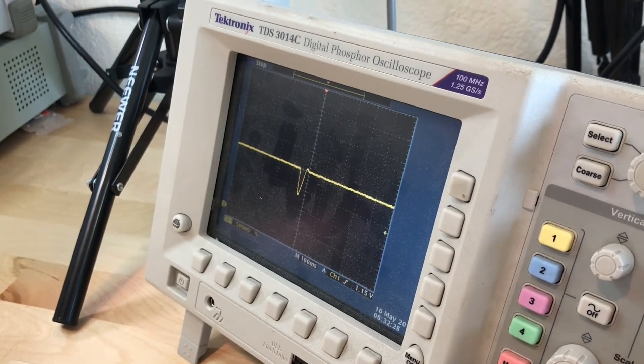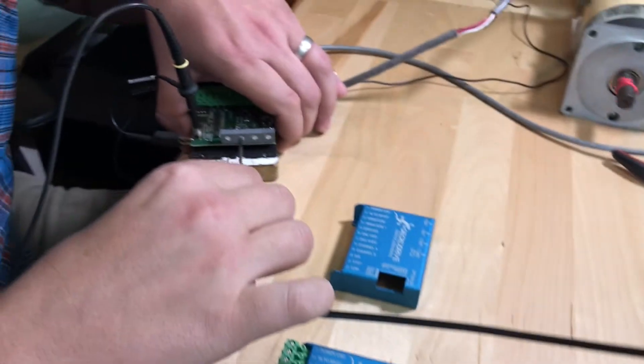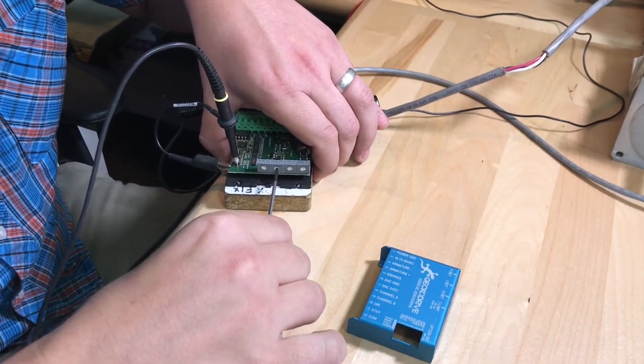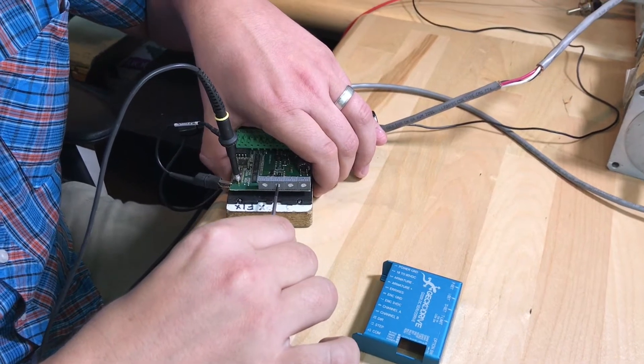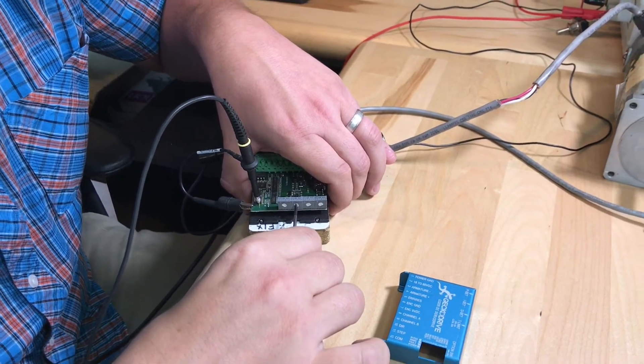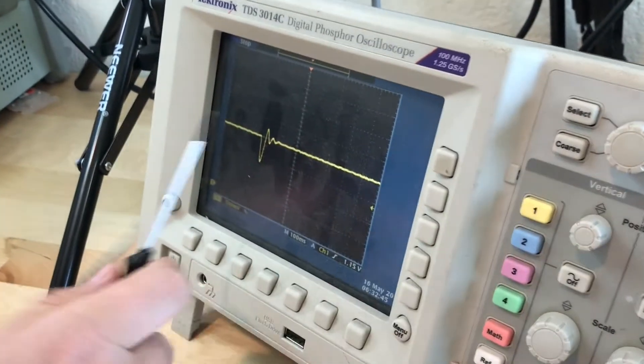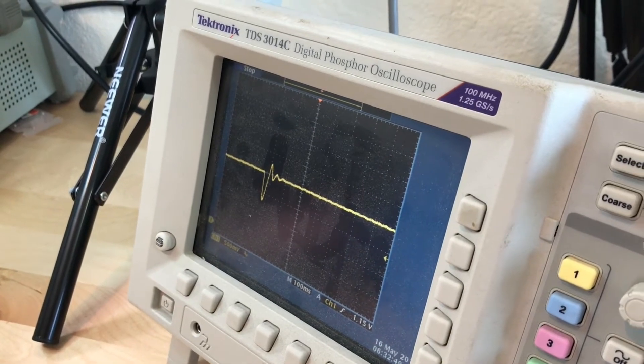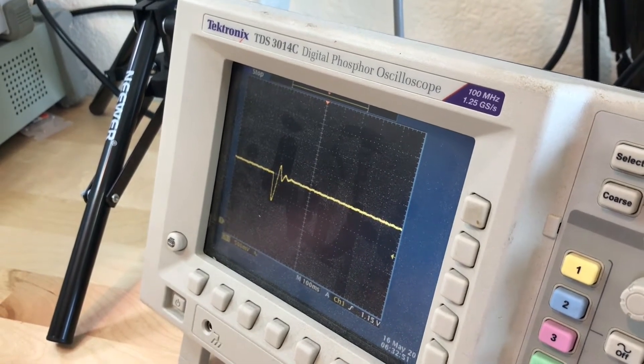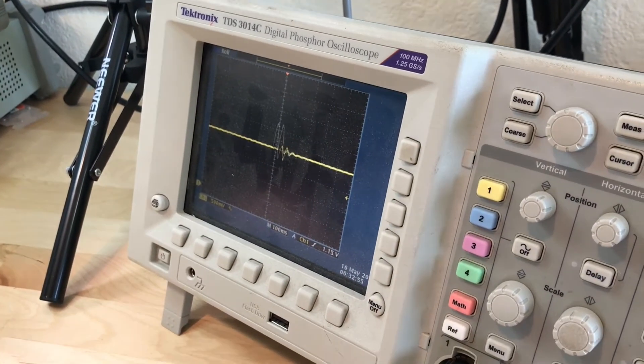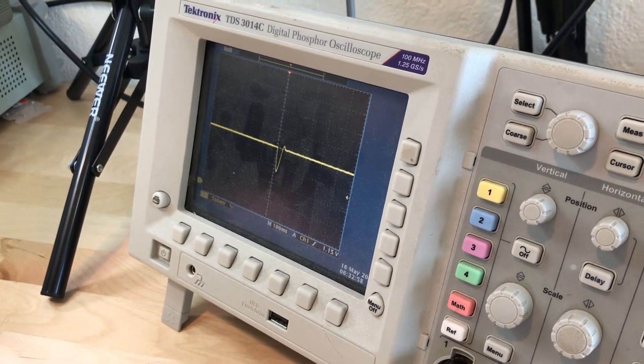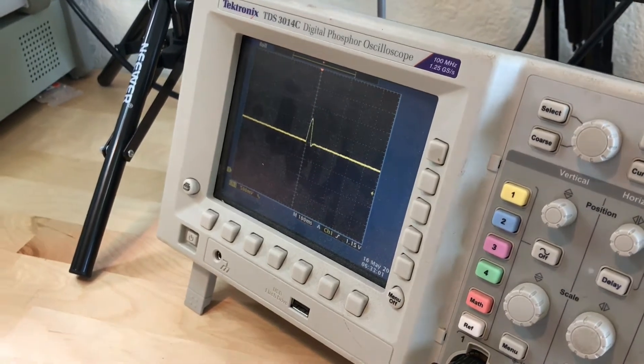Lastly, we have the D trim pot. The D trim pot should always lead the P trim pot. If it doesn't, it'll increase settling time. You can see right here the number of oscillations it takes - that's a significant time for it to settle on commanded position. Let me put it back to where it needs to be, and there we go.